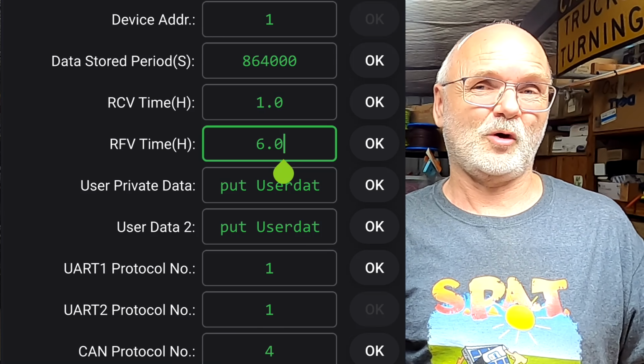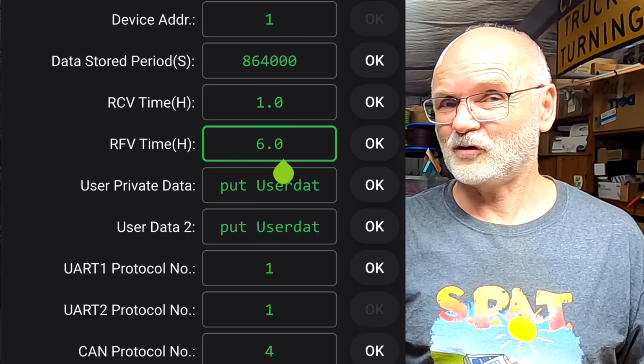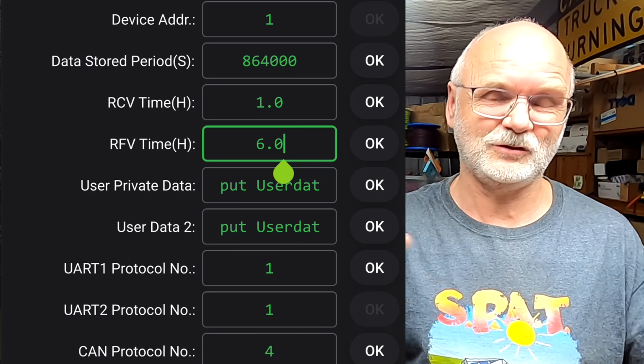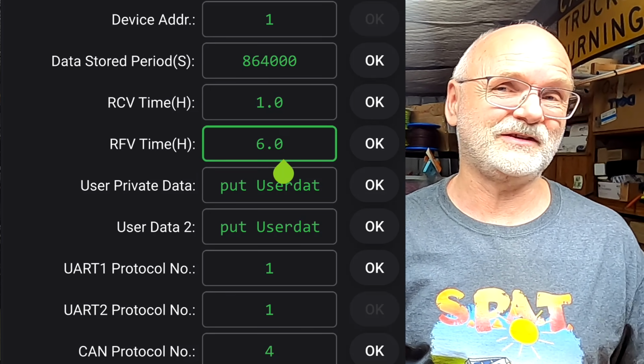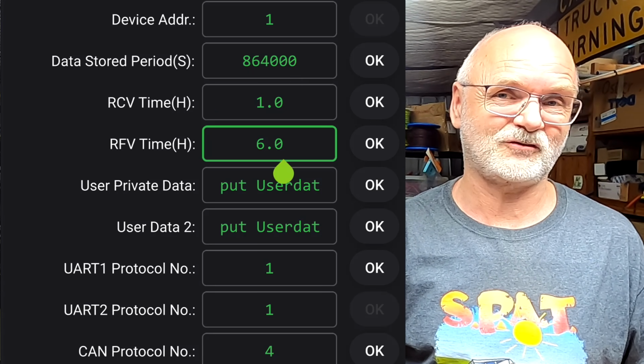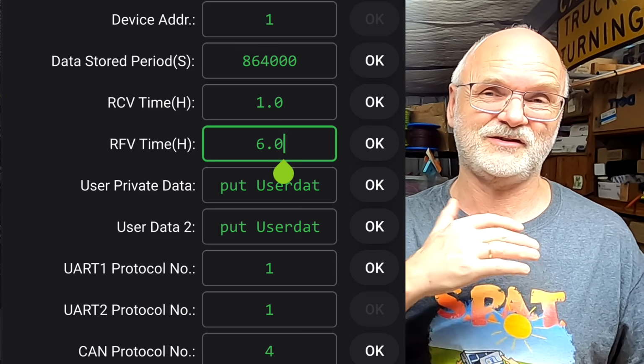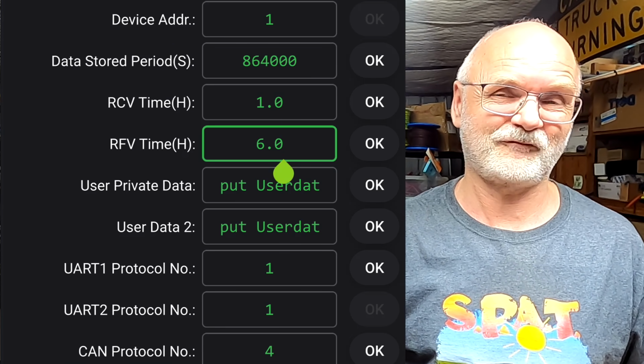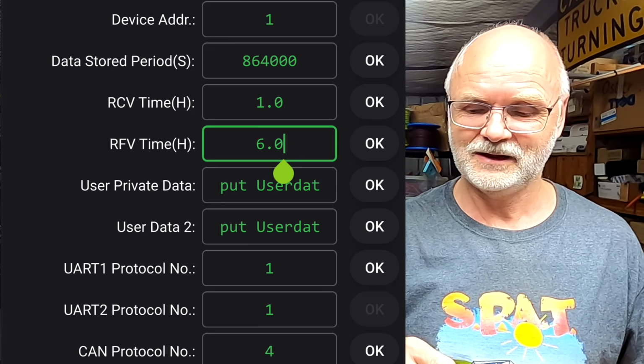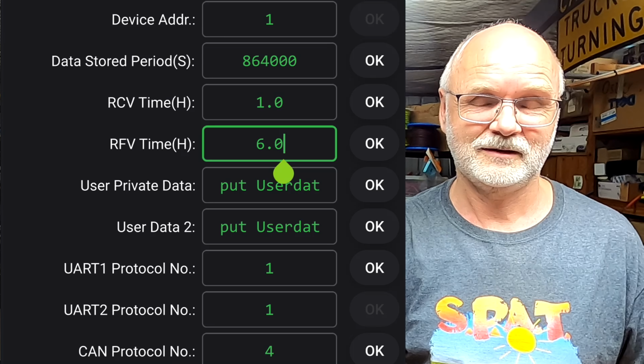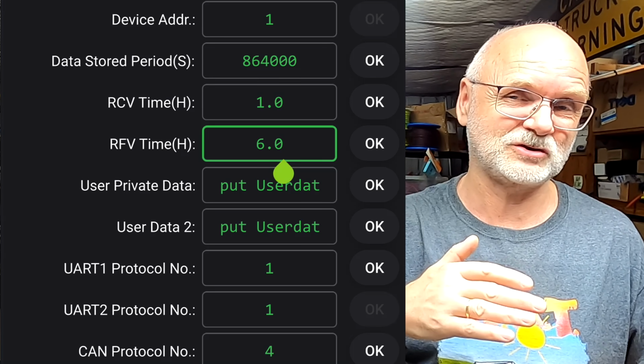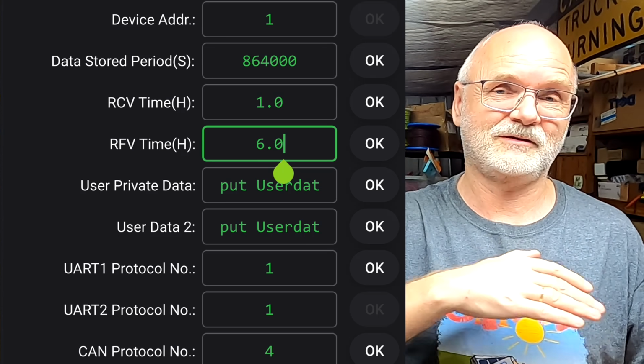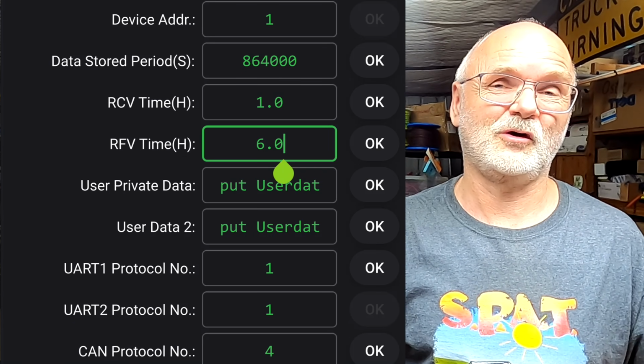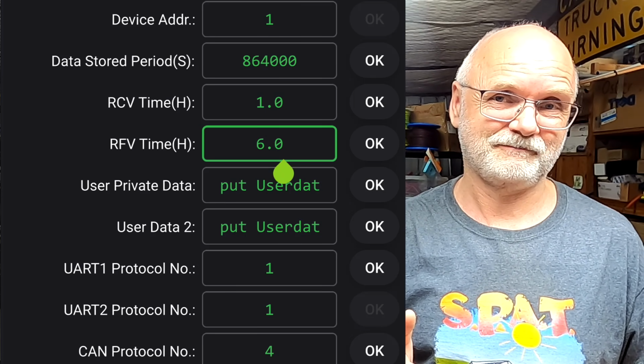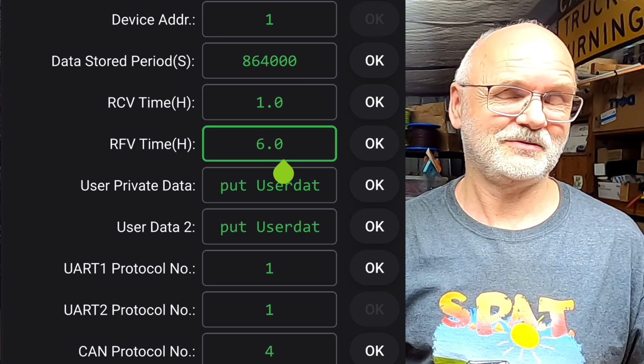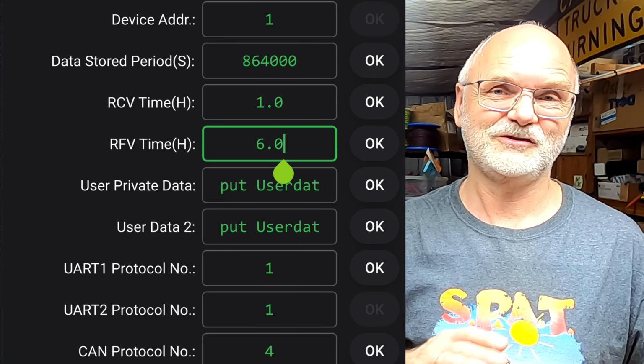Honestly, I don't see the point of having a tail current if you have a timer. Victron has got both, and you can disable either or use both as you want. But this is probably a discussion we should have in a separate video, whether it makes sense to have a tail current at all. My experience so far is a tail current doesn't make sense, especially not when you have a mix of sun and cloud during the day and you charge with different currents into your battery. Very easily you can go under the tail current threshold and the BMS thinks, oh, we are fully charged, and goes to float mode, while outside it was only a cloud in front of the sun that lowered your charge current. That's why I think a timer is far more consistent, since it runs regardless of how fast or slow you charge.